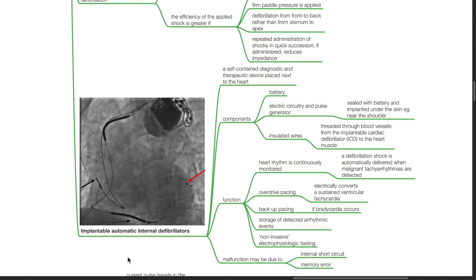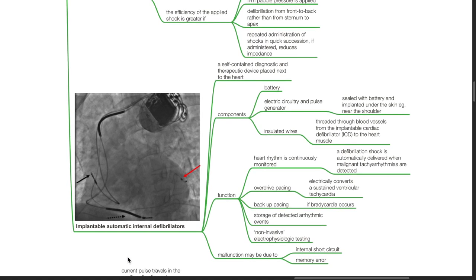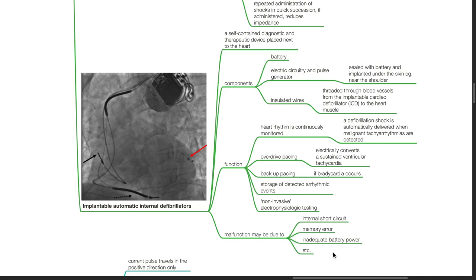Implantable automatic internal defibrillators are self-contained diagnostic and therapeutic devices placed next to the heart. Components include battery, electric circuitry and pulse generators sealed and implanted under the skin near the shoulder, and insulated wires threaded through blood vessels to the heart muscle. Functions of ICDs include continuous heart rhythm monitoring, automatic defibrillation shock delivery when malignant tachyarrhythmias are detected, overdrive pacing to convert sustained ventricular tachycardia, backup pacing if bradycardia occurs, storage of detected arrhythmic events, and non-invasive electrophysiologic testing. Malfunction may be due to internal short circuit, memory error, inadequate battery power, etc.